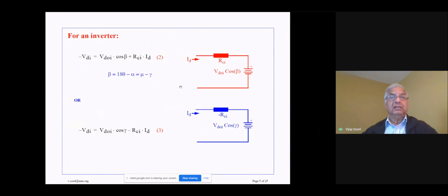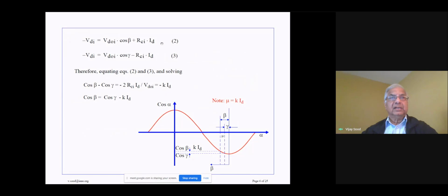There are some more details about the inverter end. So beta is defined as 180 degrees minus alpha is equal to mu minus gamma. Mu is the commutation angle, which is described by the voltage drop over at the inductance. So either using beta or gamma, we have this equation. With beta, we have equation number 2. So these two circuits can define the behavior of the inverter. Normally, we utilize this configuration to reduce the reactive power consumption. The extinction angle is maintained constant at the inverter. So these two equations again describe the behavior, and they are linked in this fashion.